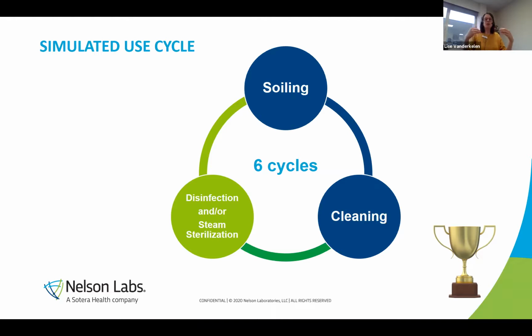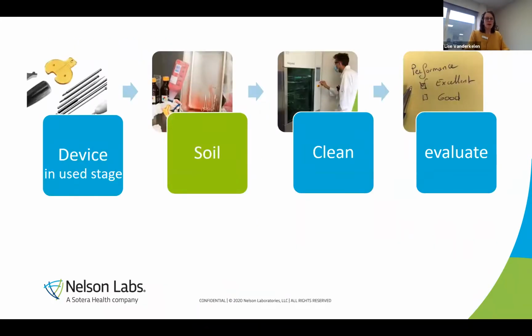Why? You need to bring the device into a use stage where you soil, clean, and disinfect or sterilize your device a numerous amount of times in order to allow soil to build up. We at Nelson use 6 cycles. You can do more, but you have to make sure that soil is allowed to accumulate to make sure that you challenge your procedure. Okay. So we have discussed our device and we know what we need from the device point. We need it in use stage.